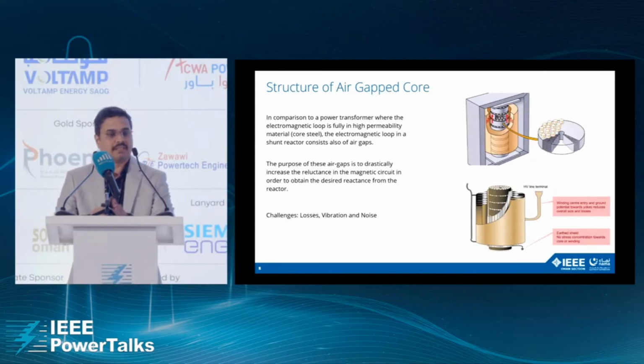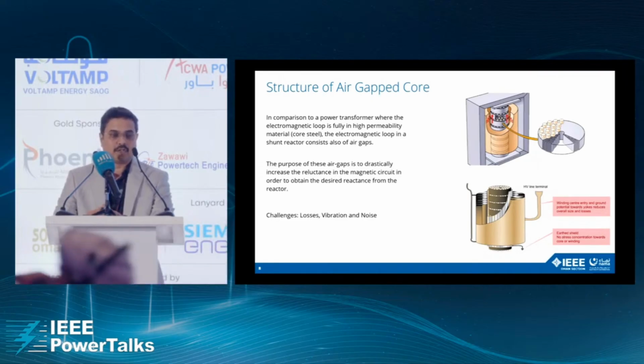Now coming to the construction, it's similar to a transformer, where you have a winding and a core. The only difference is that normally in a transformer we have multiple windings, because it works on the principle of mutual induction through electromagnetism, and we have a very high permeability core. In the reactor we do the opposite. We have the core with very high reluctance, so we want to reduce the permeability of the core. And second, most important, we have higher air gaps in the core. You can see a few air gaps in the core which we are constructing. These air gaps are important to maintain the high reluctance of the reactor, which is the desired function of this shunt reactor, and these air gaps can absorb the reactive power from the system.